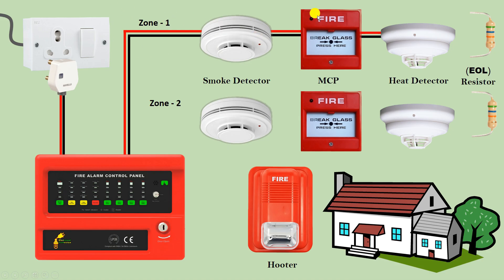In zone 1, connect as many detectors as you need in this looping manner. At the last detector, bring both wires and do the connection with the EOL resistor.